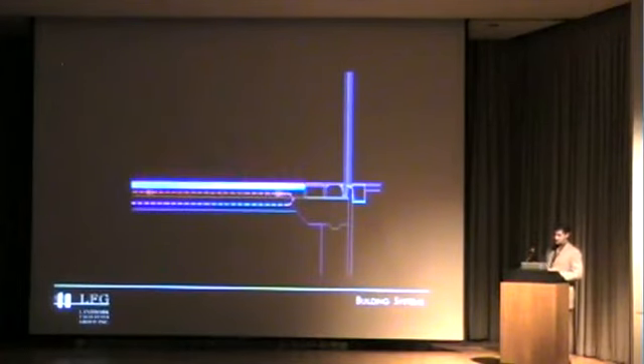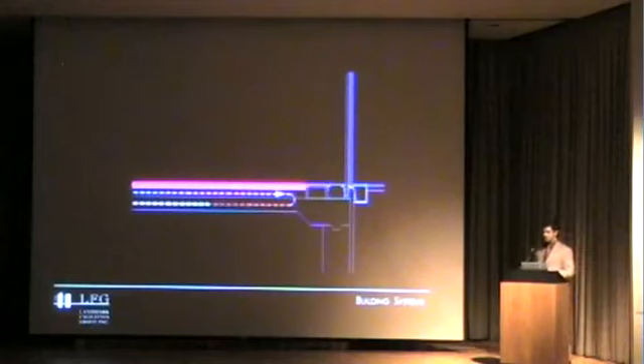Now, by having this radiant system, we are also allowed to do what people are apt to call radiant cooling, but I prefer to call it radiant heat absorption. Essentially, as the exterior sun comes in and warms this floor up, we don't want it to radiate into the space and add to our cooling loads. So we can run tempered water through the radiant slab and draw away that solar heat and put it back into the system, taking that load out of the equation. It eliminates the glass load, which is huge when we're trying to design a system, because it allows us to reduce that size and make everything a lot more energy efficient.